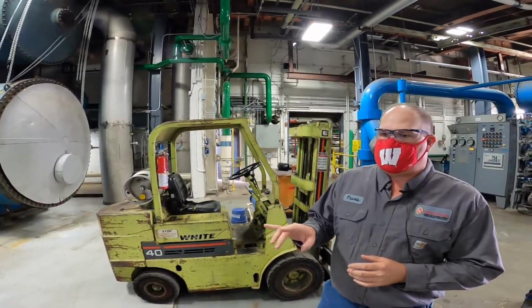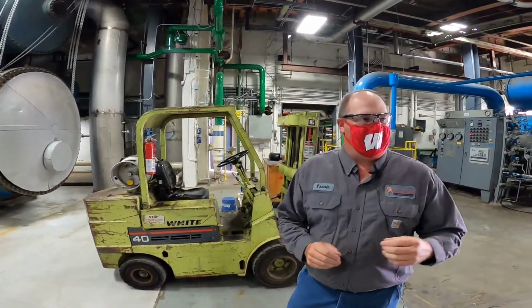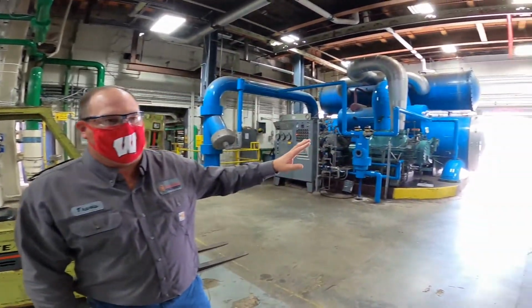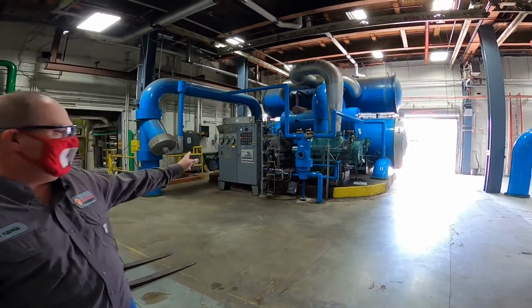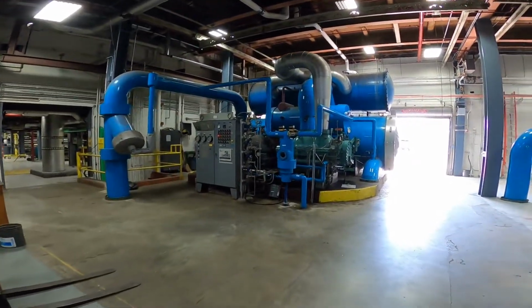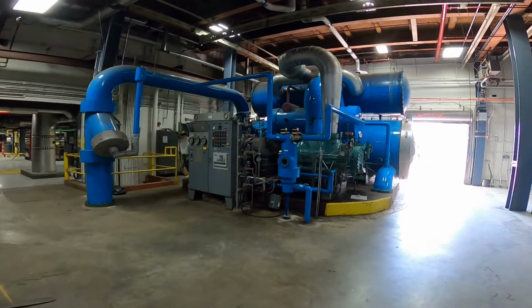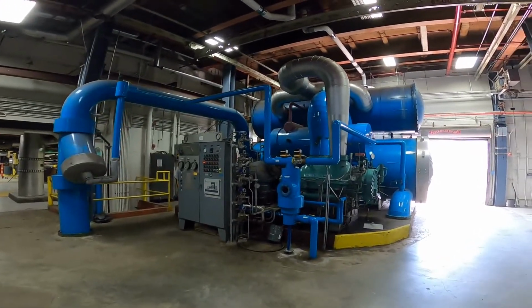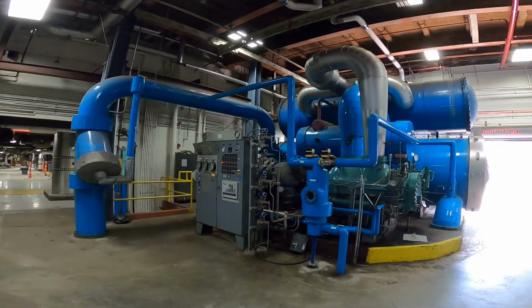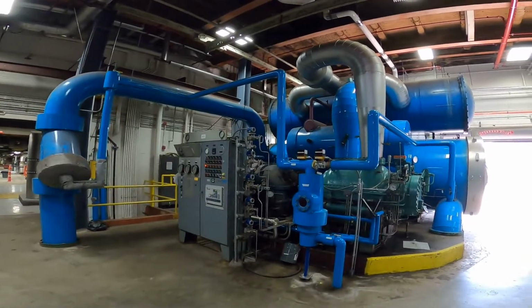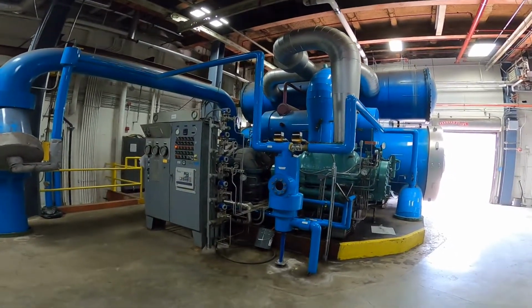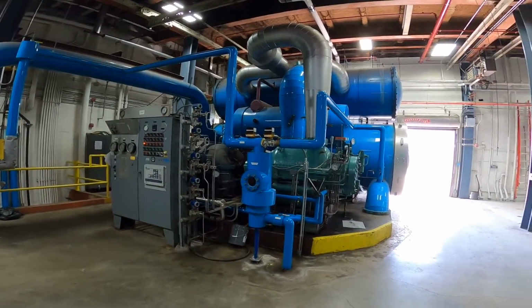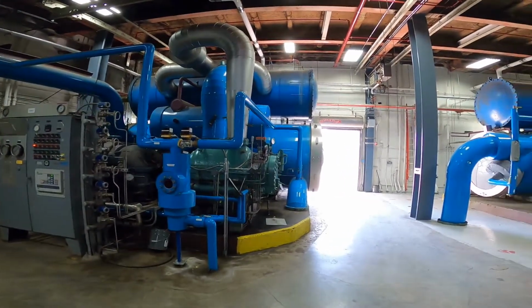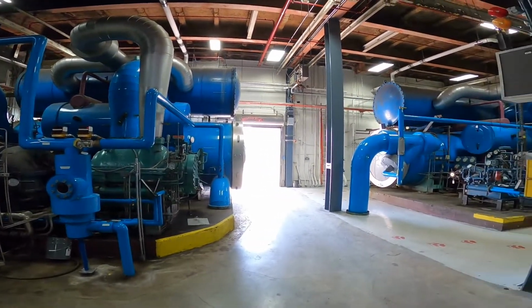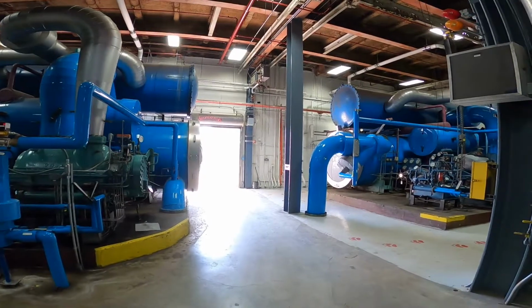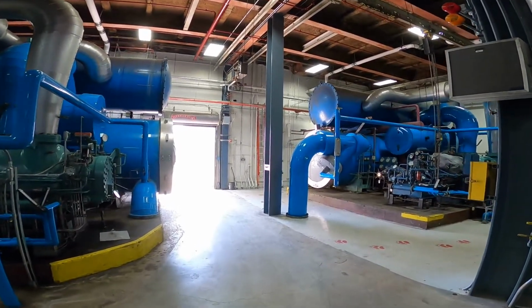We have 2 of these chillers in this facility, and then we have 2 other chillers that are half the size, 4,000 tons of capacity, chillers 1 and 2. Again, tons, Travis, what do you mean by that? That's ton hours, so that's the amount of load it can produce. If you want equivalent to like a house, your standard household unit's anywhere from 1.5 to 2.5 tons. So you can look at it that one of these small chillers can do 2,000 homes.